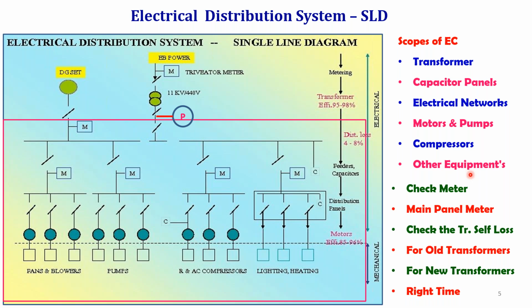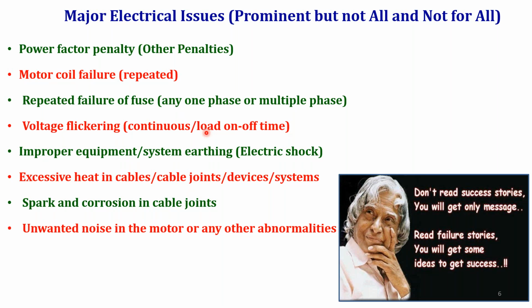And this is the right time to check whether your transformer losses are within the controlled value or not, because the pandemic situation has given the maintenance people more time to take the readings on the transformer side, primary side as well as secondary side.